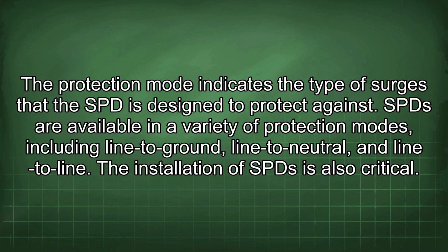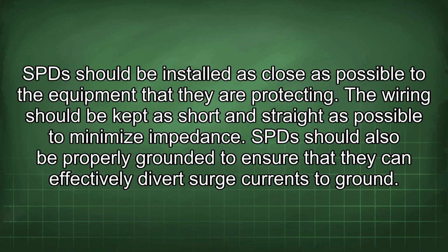The installation of SPDs is also critical. SPDs should be installed as close as possible to the equipment that they are protecting. The wiring should be kept as short and straight as possible to minimize impedance. SPDs should also be properly grounded to ensure that they can effectively divert surge currents to ground.